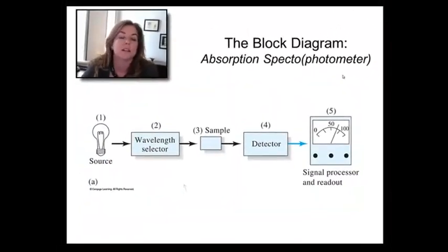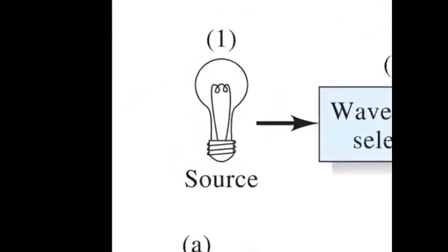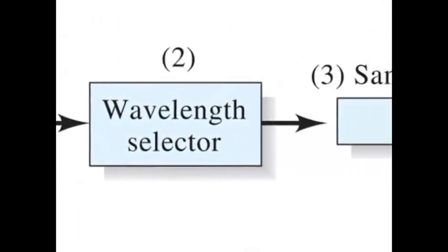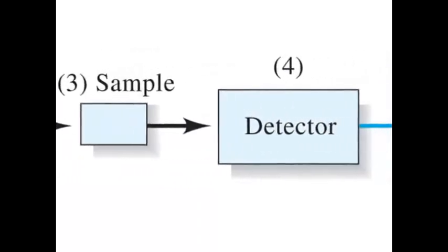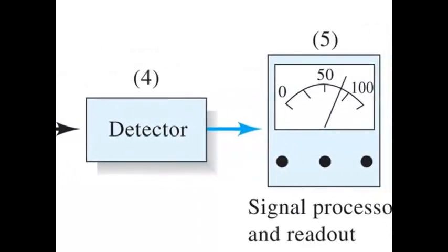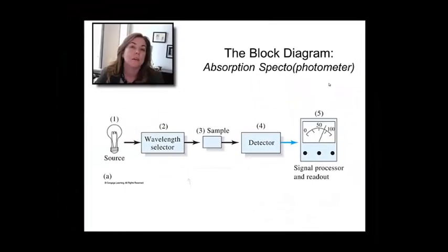Now, if you open up the guts of this thing, this is what you would see. You need to have a source of radiation, a light source. You need to select out a wavelength. You need to interact with your sample, so you have to think of the sample pieces. You've got to detect the light and then convert that to a signal that you can read. There's a couple of things about the simple diagram that are going to be changing as we go through our conversation about spectrophotometers.